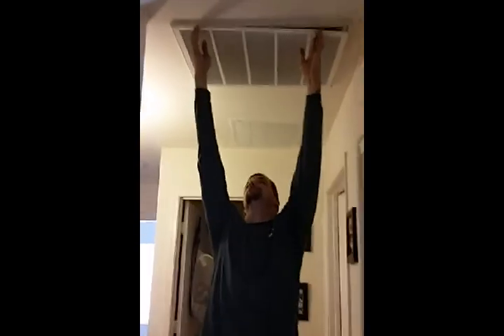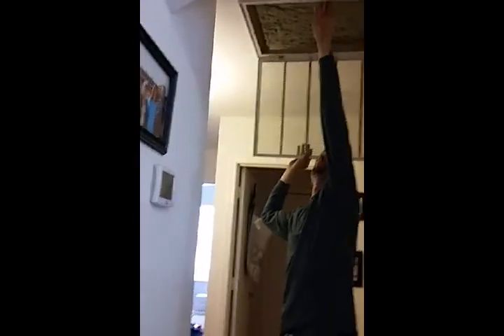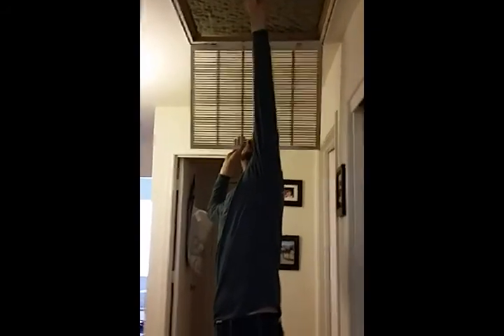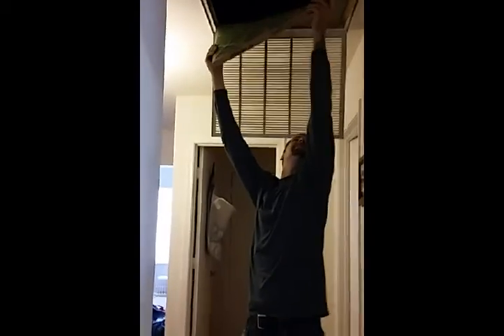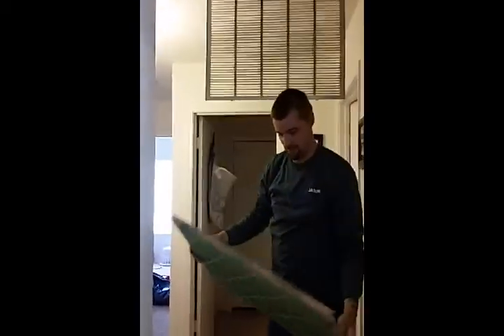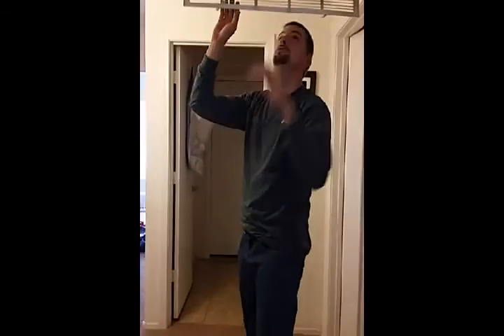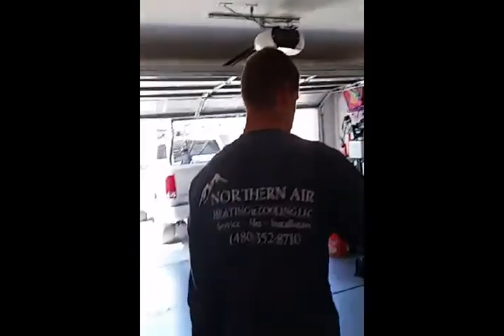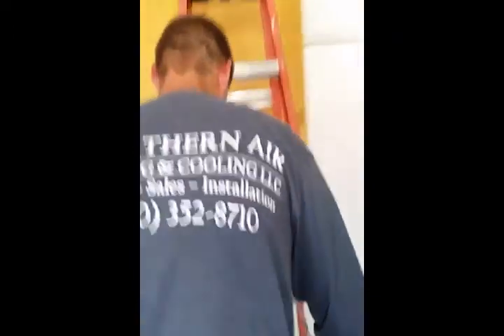Okay, now one really important aspect is to make sure that the filter is clean. You want to change it once a month, okay? This one needs to be changed. It's not the cleanest, it's not the dirtiest. You can still see through it, but it needs to be changed. So I will have the homeowner try to find me a filter so I can install it back in place. And we also supply filters at an extra charge. Usually the homeowner does have a spare.